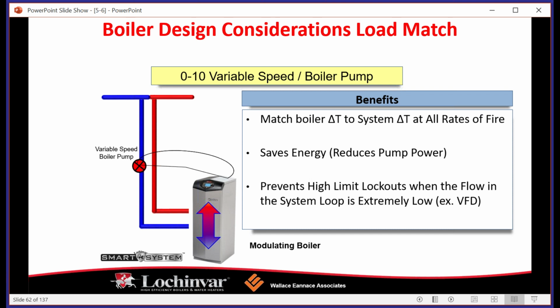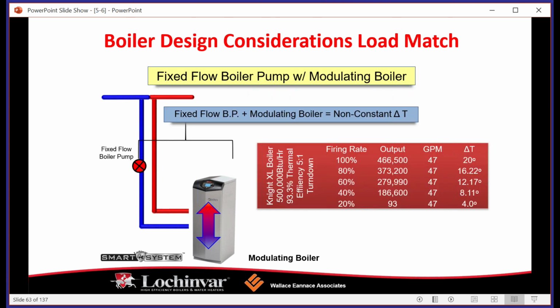The thing we need to remember is that we need to match the boiler delta T to the system delta T. And the way we do that is by using a variable speed boiler pump. So as the boiler starts to ramp up and down with its fire rate, if our pump is a fixed flow boiler pump, the boiler's still going to work, right? It's still going to heat the water. However, the problem is that you're going to start losing your efficiencies because your GPM is going to stay the same, but your output at different firing rates is going to be different, right? So you're not going to be as efficient, okay?